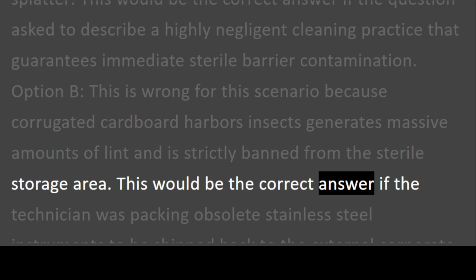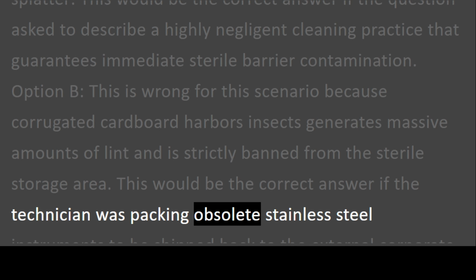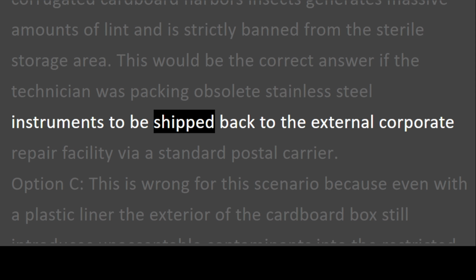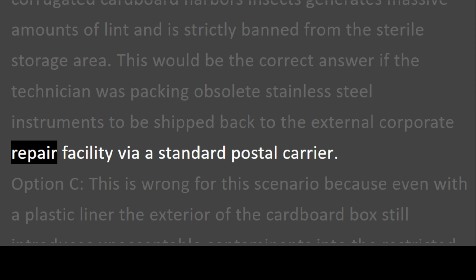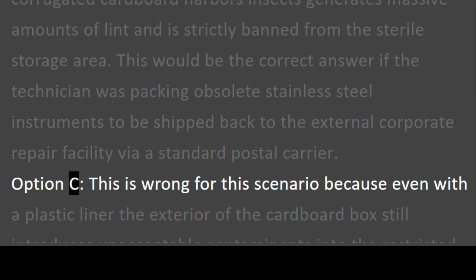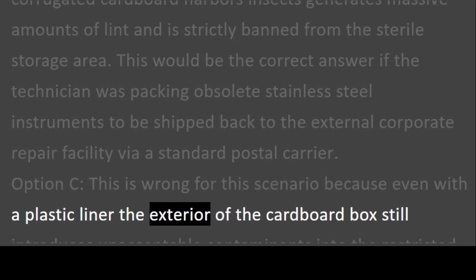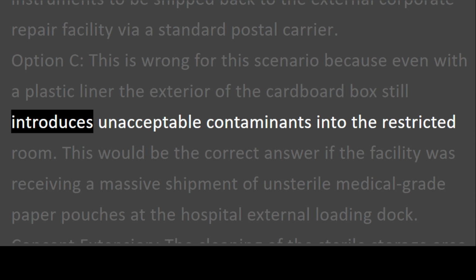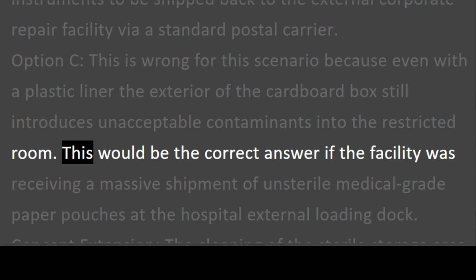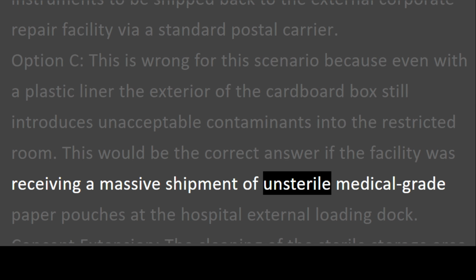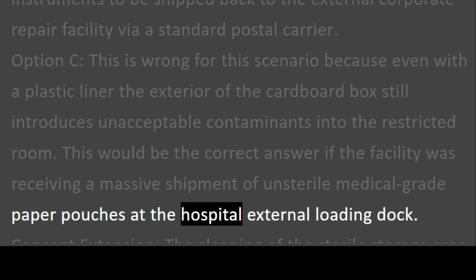This would be the correct answer if the technician was packing obsolete stainless steel instruments to be shipped back to the external corporate repair facility via a standard postal carrier. Option C. This is wrong for this scenario because even with a plastic liner, the exterior of the cardboard box still introduces unacceptable contaminants into the restricted room. This would be the correct answer if the facility was receiving a massive shipment of unsterile medical-grade paper pouches at the hospital external loading dock.